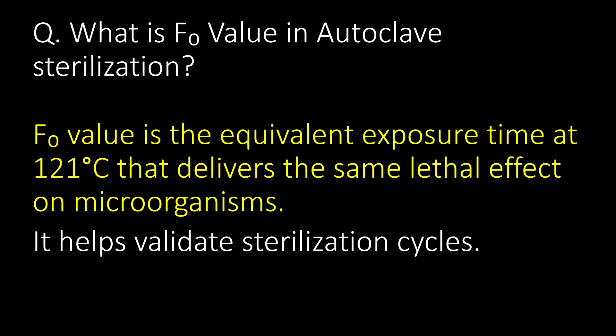What is F0 value in autoclave sterilization? F0 value is the equivalent exposure time at 121°C that delivers the same lethal effect on microorganisms. It helps to validate sterilization cycles.